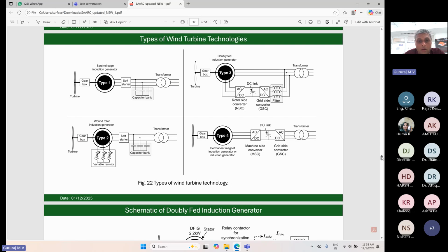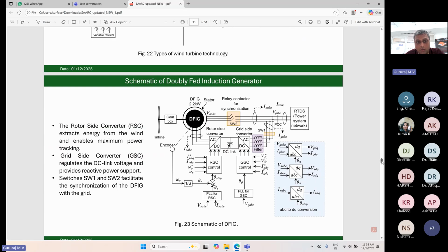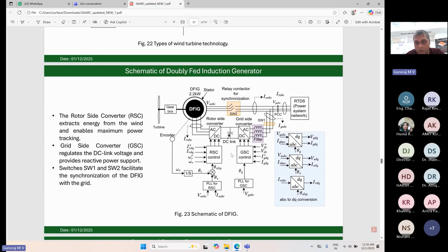So these are some schematics of the different types of generators: type 1, type 2, type 3, and type 4. You can see here a double-fed induction machine where the rotor is connected to the point of common coupling via these back-to-back converters, which can render various support. So this is a schematic of the double-fed induction generator.